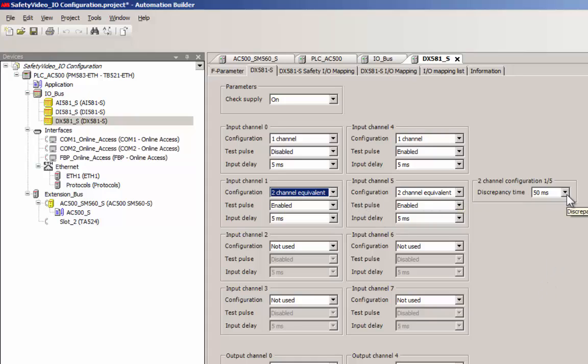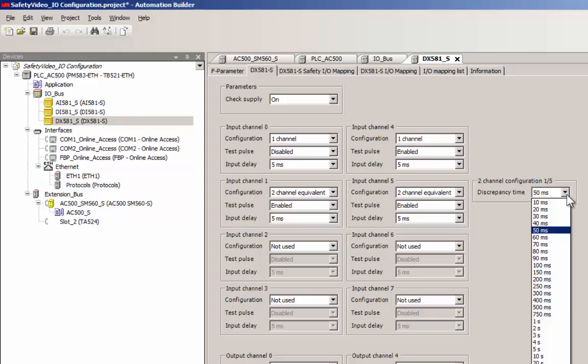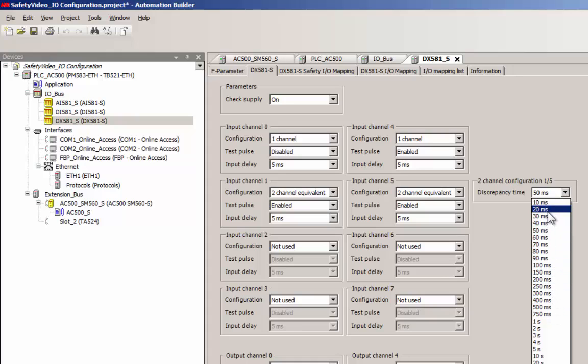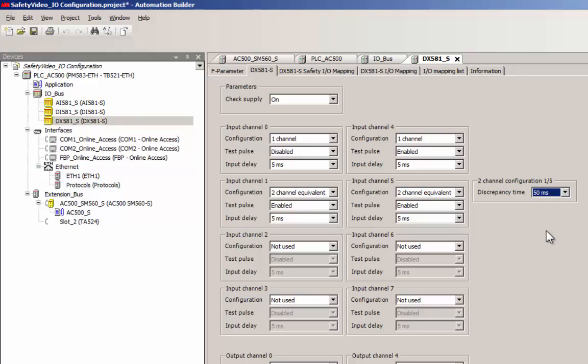Appropriate value at the discrepancy time parameter is set to capture signal mismatch between channels. If the signal mismatch situation continues beyond this value, it would be sensed by the module and acted upon with a channel passivation or a safe state.